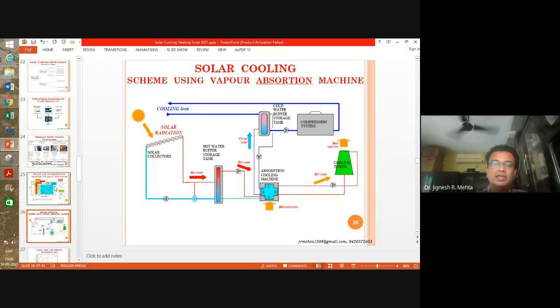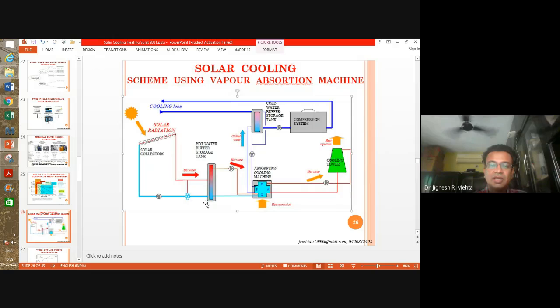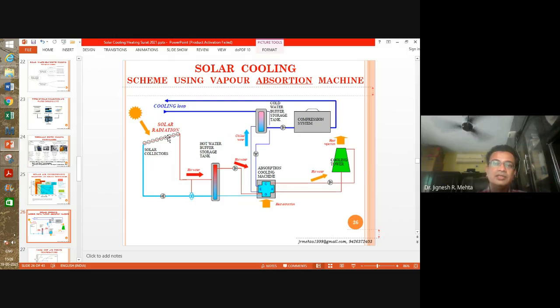So solar cooling, this is the cycle or the scheme. I think this can be easily understood by you. The solar collector, then the storage would be there many times, or most of the times. Then you run your absorption chiller, so the generator, absorber, condenser and evaporator, and normally a cooling tower is used for such absorption chillers. And again, chilled water storage can be there. Many times, most of the times, you have to support it with the vapor compression system because of uncertainties related to the solar collectors. And then this is the cooling loop.